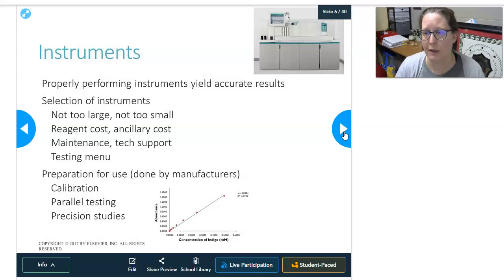But if you are in a hospital lab that's running 24/7, then you're going to want 24/7 tech support. And what's the response time for sending a tech out there to fix your machine and all of that? Then also, what's the testing menu, and that will be driven by the type of lab that you have and the needs of the physicians and the patients in that setting. And then, can that instrument accommodate your testing menu? All those are things that go into selecting an instrument, and getting the right instrument in the lab is really important to quality.